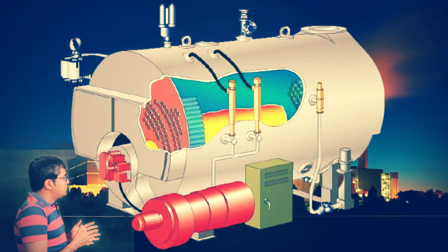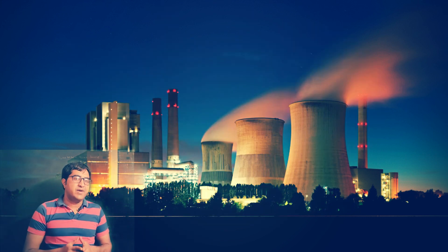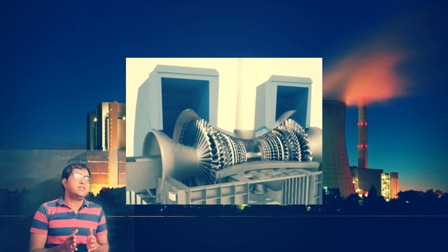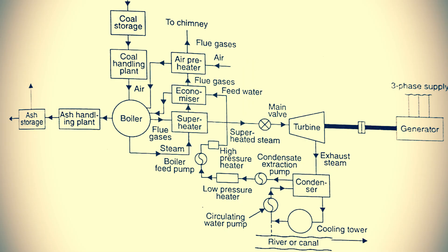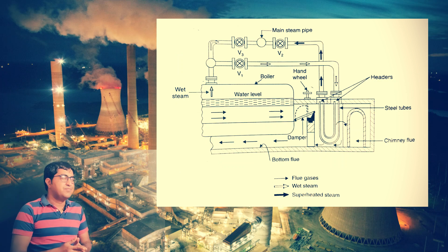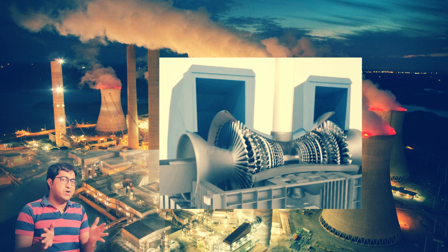Whatever steam is produced in the boiler — whether wet or dry steam — we cannot directly supply it to the turbine, because moisture content in the steam will erode and corrode the turbine blades. So this steam passes through the superheater. The superheater is located in a higher temperature range; it removes all the moisture from the steam and converts it into superheated steam.